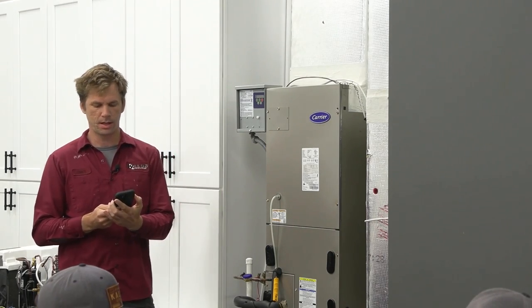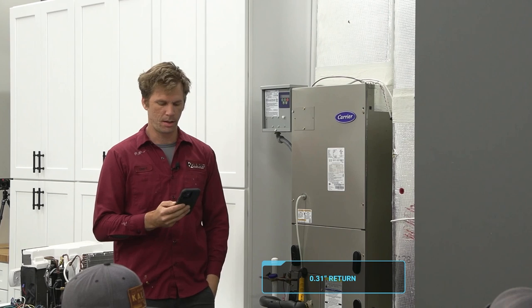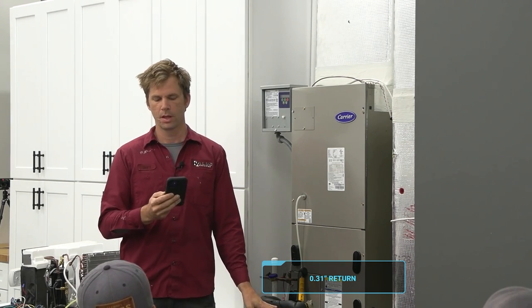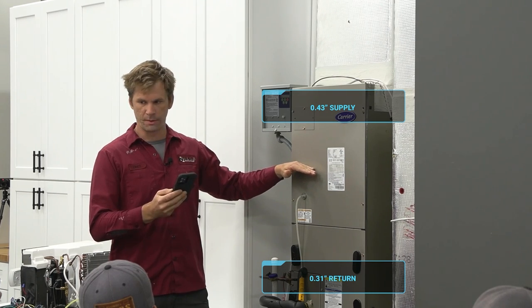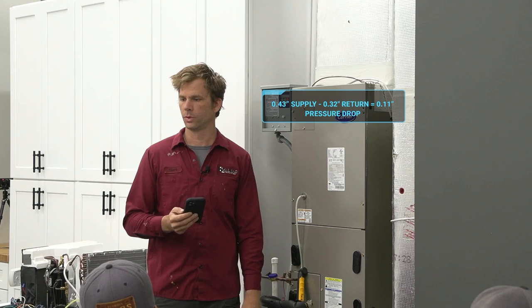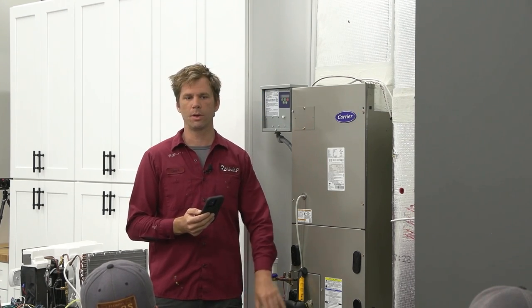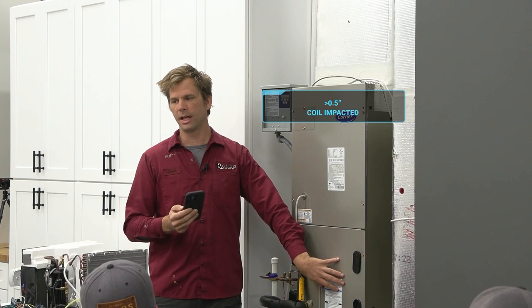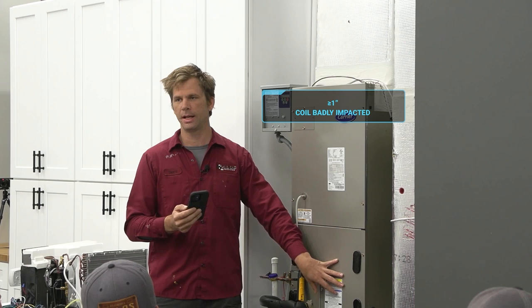I have 0.31 below the coil and then 0.43 above the coil. We have about a 0.1 drop on a wet coil.